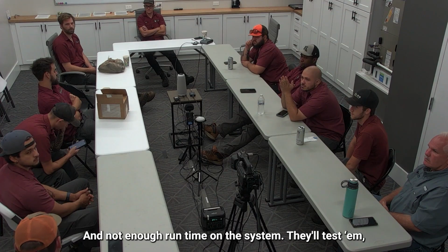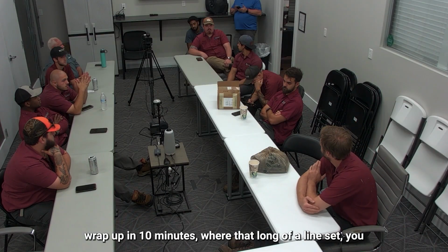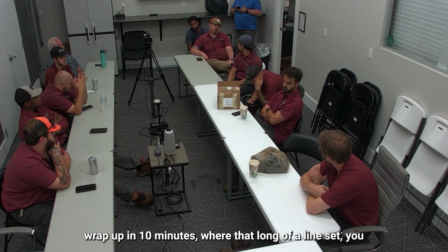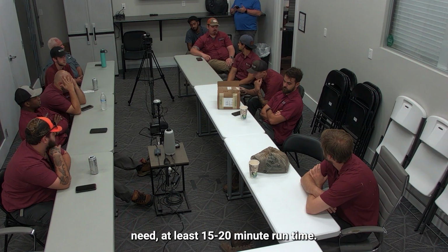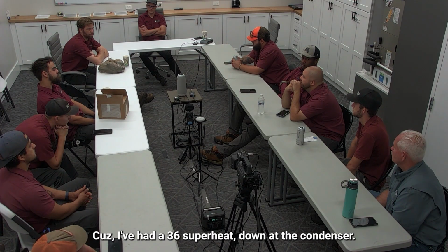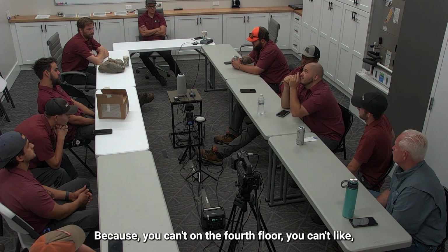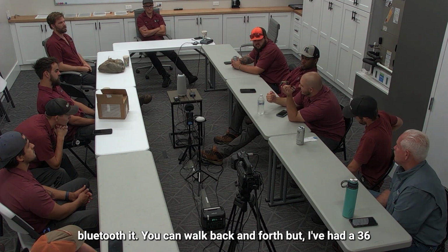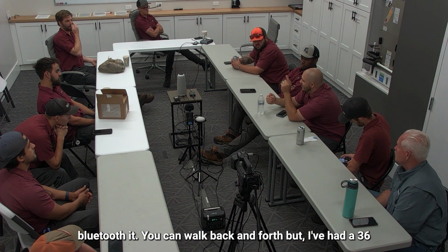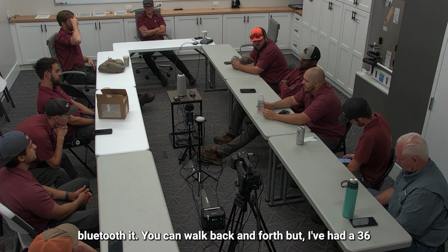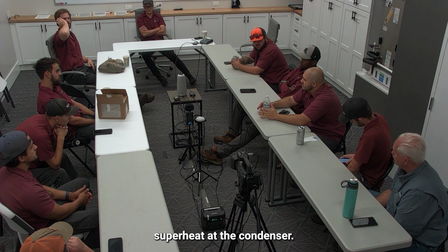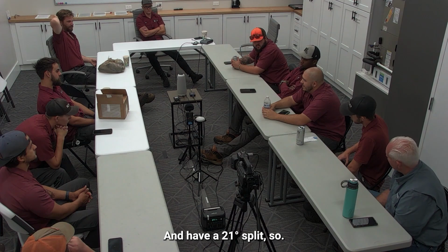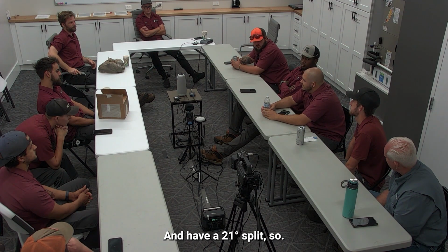And not enough runtime on the system. They'll test and wrap up in 10 minutes, where with that long of a line set, you need at least 15-20 minutes runtime. Because I've had a 36 superheat down at the condenser, because on the 4th floor you can't just Bluetooth it. You can walk back and forth, but I've had a 36 superheat at the condenser and completely happy, a 21-degree split. Yeah, that's a good word.